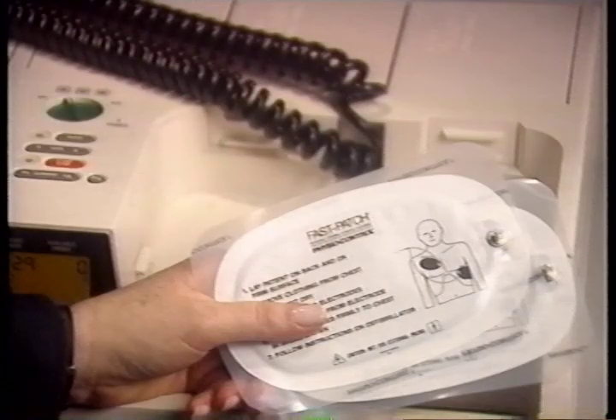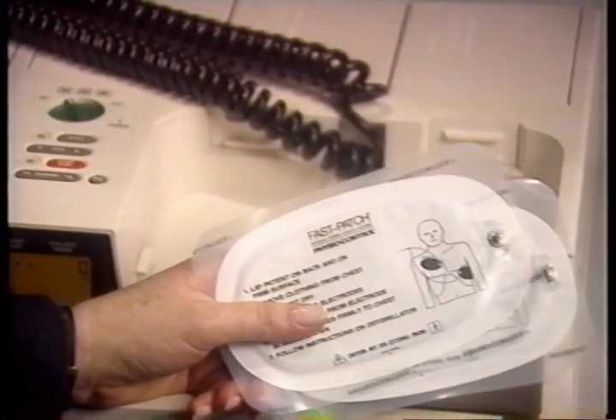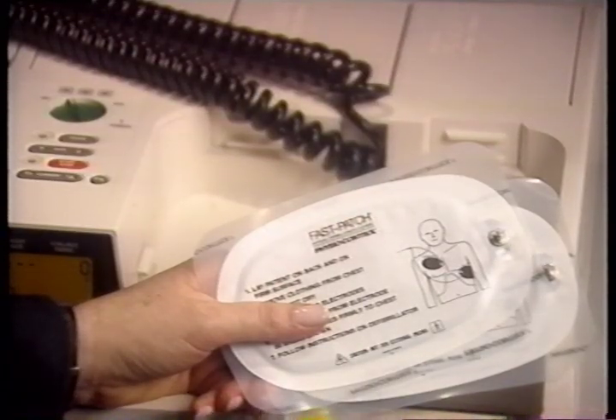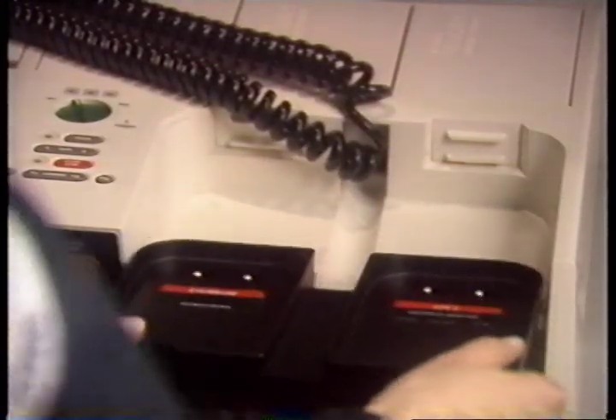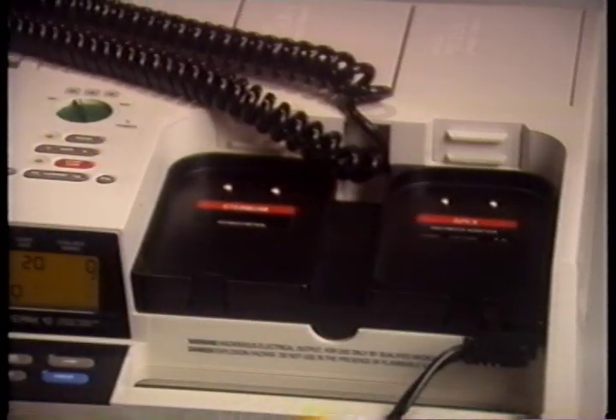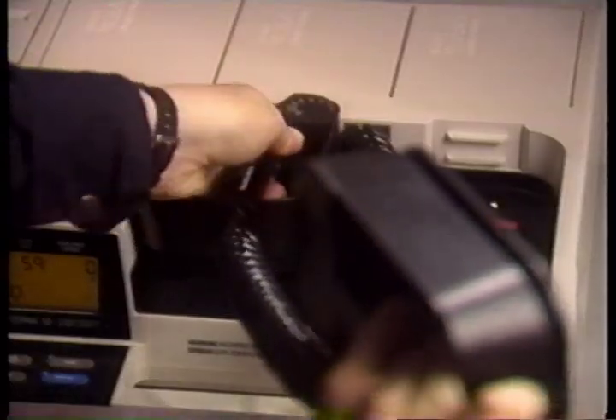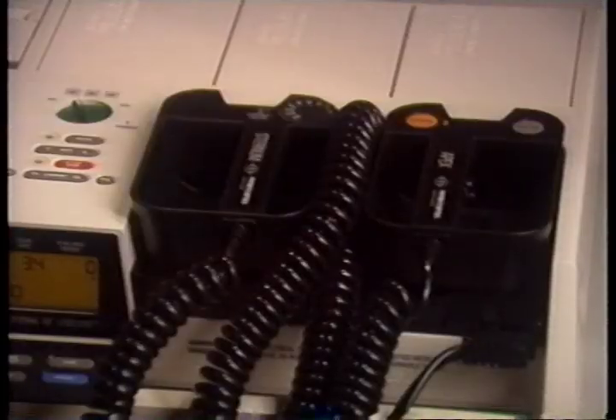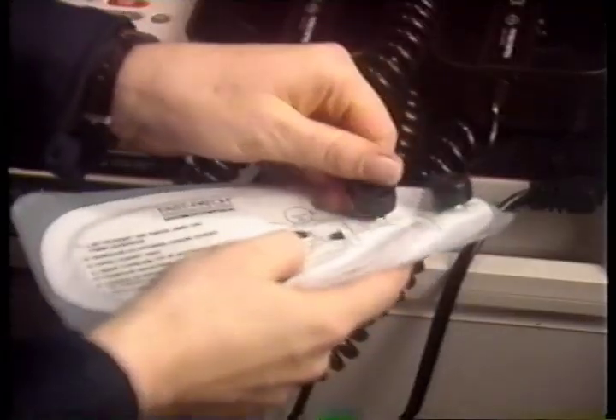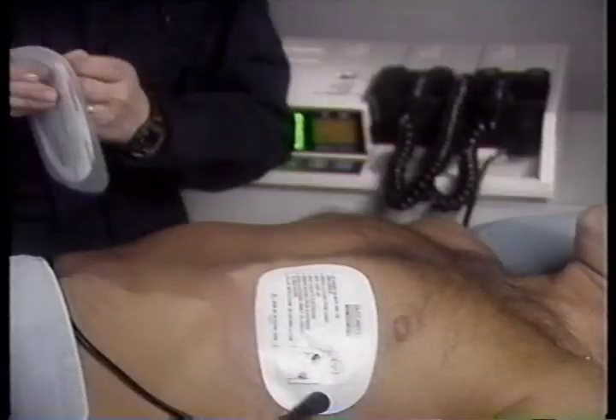The optional fast patch adapter lets you use fast patch disposable defibrillation electrodes with your LIFEPAK 10. These electrodes allow you to monitor, defibrillate, or cardiovert. To install the adapter, remove the standard paddles from their storage area and insert the fast patch adapter. Place the standard paddles back into the fast patch adapter. Snap the cable ends onto the defibrillation electrodes. Apply the defibrillation electrodes to clean, dry skin in the standard apex sternum position.